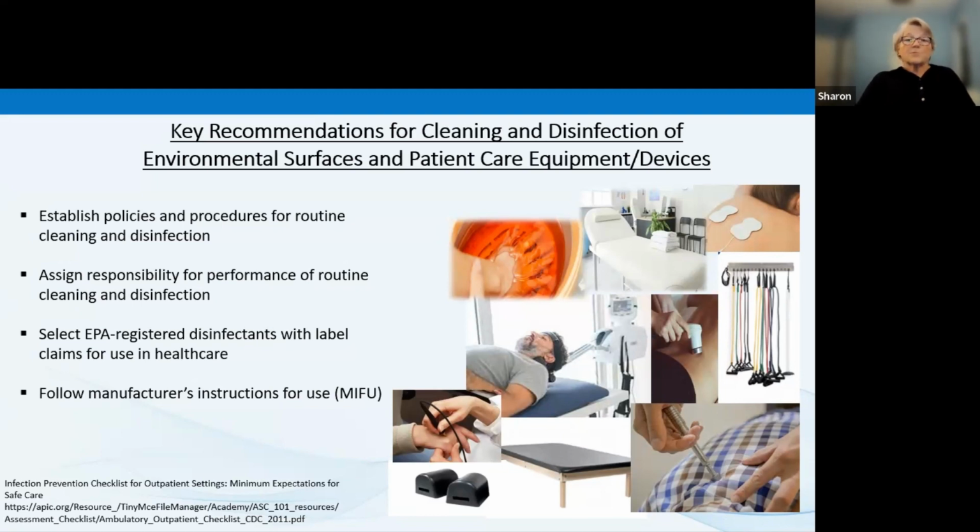Competencies of care providers responsible for cleaning and disinfection of equipment and devices should be documented initially upon assignment of those duties, annually, and whenever new devices or disinfectant products are introduced or policies and procedures change. So it's not a one and done, it's a continuous process.